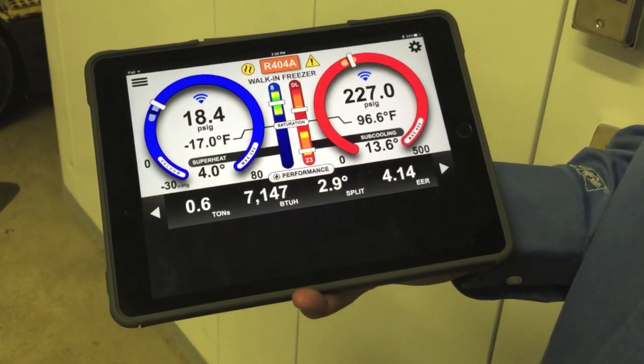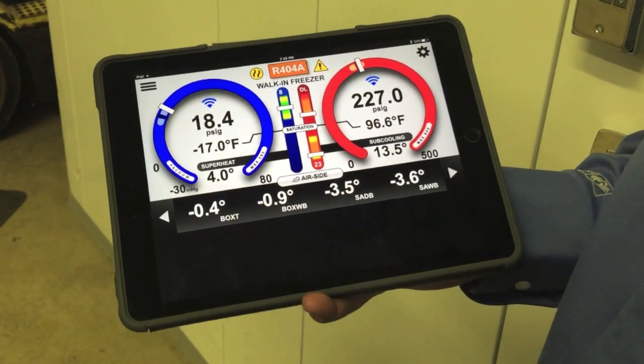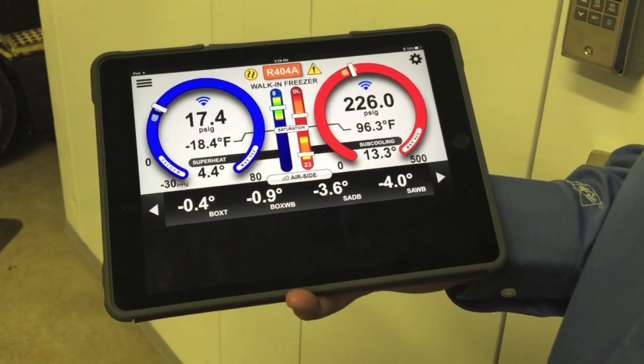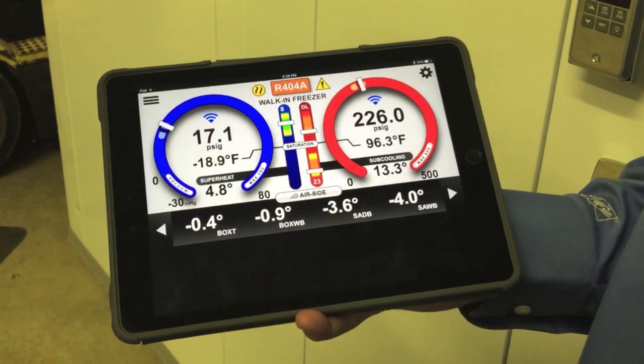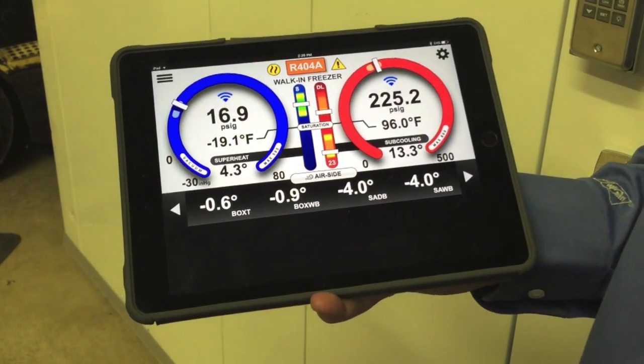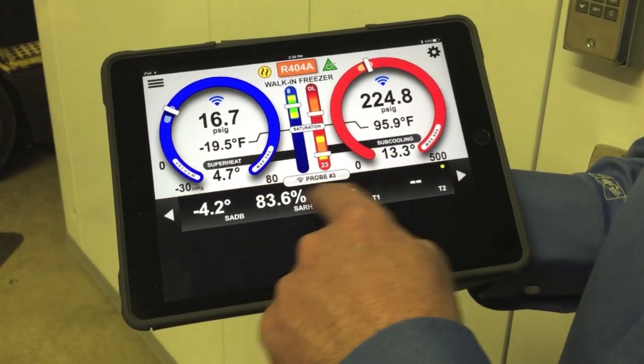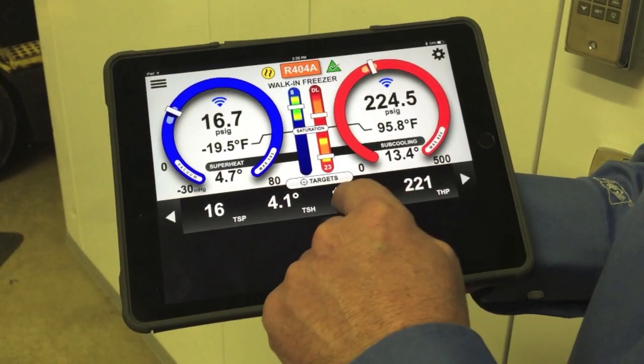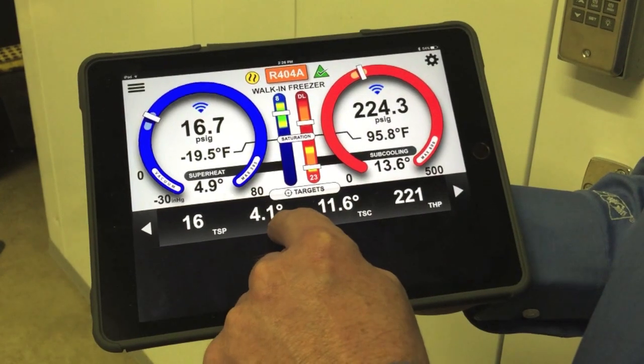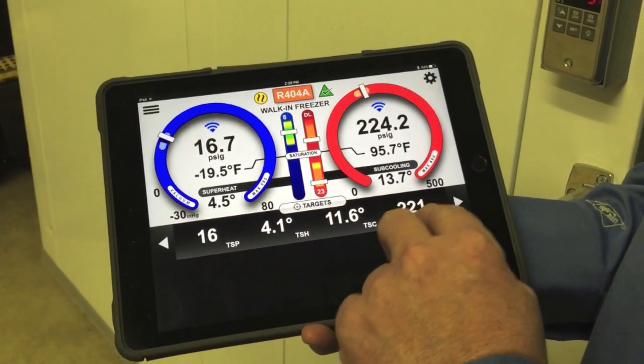The machine just started up. We're a few degrees off set point. Our box temp is at about zero degrees — we're looking for it to be around negative 8 to negative 10 when it satisfies. You can see very quickly that our pressures are falling into the right ranges. The I-Manifold calculates our targets. Scrolling through to targets, we're looking for a target suction pressure of about 16, target superheat of 4.1, subcooling of 11.6, and high pressure of 221.